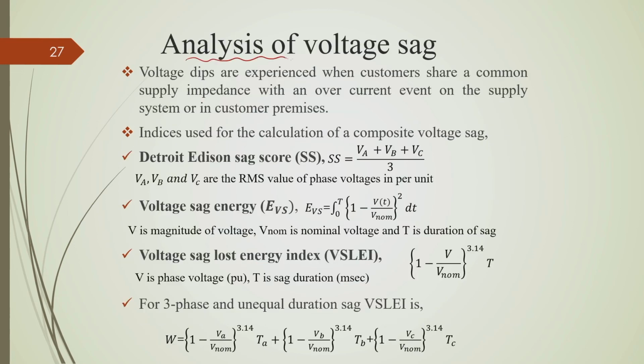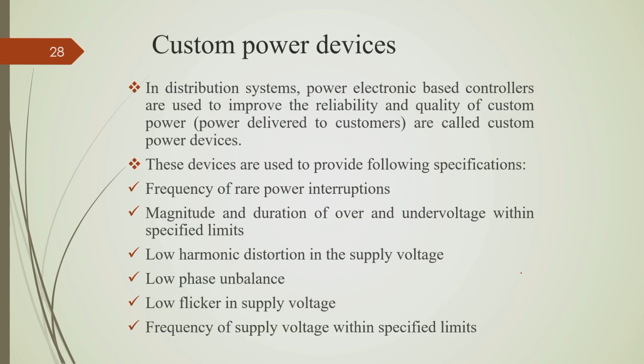Now, these are some of the ways we can categorize voltage sag. Many people did research on characterizing this. One is called the Detroit Edison sag score, where simply the magnitudes of the 3 phase voltages are summed and divided by 3. So, if any of the phases is sagging, then the magnitude of that phase voltage would be lower than the nominal voltage. So, this score will be lesser than 1, and if there is no voltage sag, it will be equal to 1. Similarly, some people consider voltage sag energy to quantify voltage sag, and people have used different indices to quantify voltage sag.